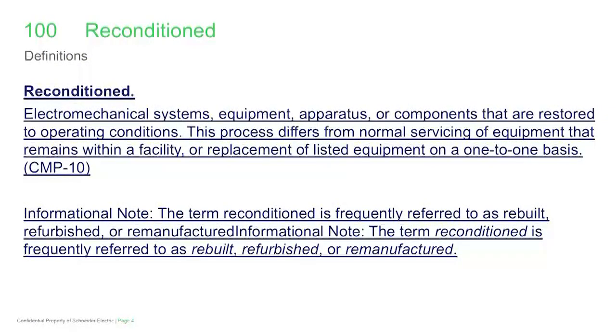The next sentence starts with: this process differs from normal servicing of equipment that remains within a facility, or replacement of listed equipment on a one-to-one basis. So we're completely differentiating reconditioned equipment from equipment in your facility that has normal servicing, normal maintenance. One example would be a low voltage power circuit breaker. We're going to bring in a contractor that is going to maintain that equipment for us. They may change contacts, springs, etc. That's normal servicing, and it does not render that piece of equipment as reconditioned.